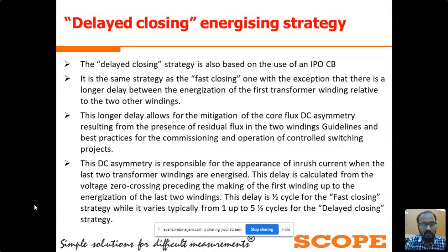This longer delay allows the mitigation of the core flux DC asymmetry resulting from the presence of residual flux in the two windings, as per the guidelines and best practices for the commissioning and operation of control switching projects. So by adding the delay, we are trying to mitigate the core flux DC asymmetry. This will help to minimize and reduce the inrush current during the charging of the power transformer.